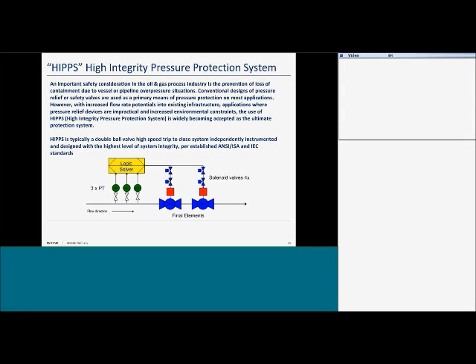So high integrity pressure protection system, typically this is what a HIPPS system looks like. Once again, you've got your sensors, logic solver, and currently you've always got two shutdown valves or final element packages. They're typically double block and bleed ball valves for the most part, although there's some great opportunity for triple offset valves in this application. That really is an area where we need to continue to educate our customers on triple offset valves and how they function and what their benefits are, so that we can see more triple offset valves installed in these applications. But really there's no reason they can't be unless the line needs to be pigged. And if it needs to be pigged, of course, now we're talking about full port ball valves.